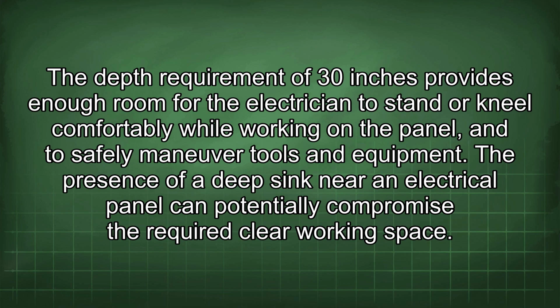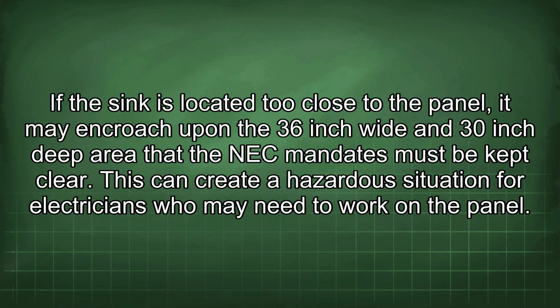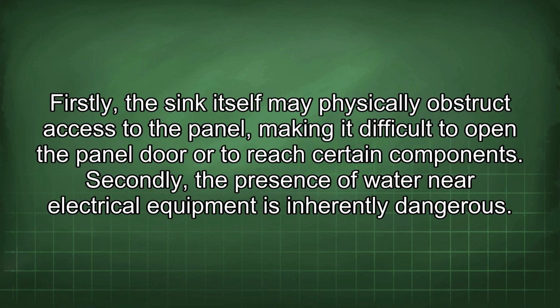The presence of a deep sink near an electrical panel can potentially compromise the required clear working space. If the sink is located too close to the panel, it may encroach upon the 36-inch wide and 30-inch deep area that the NEC mandates must be kept clear. This can create a hazardous situation for electricians who may need to work on the panel. Firstly, the sink itself may physically obstruct access to the panel, making it difficult to open the panel door or to reach certain components. Secondly, the presence of water near electrical equipment is inherently dangerous.